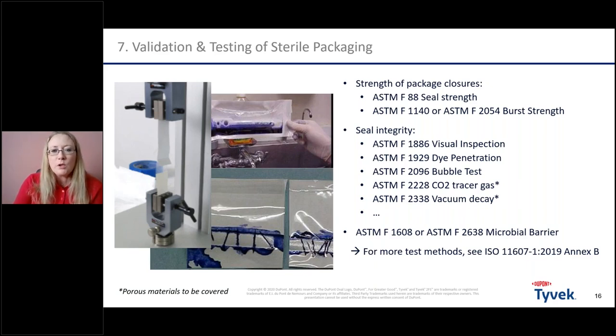Some also use burst strength testing, an overall strength test to see how much pressure the packaging can withstand. Then you need to evaluate seal integrity or integrity of the packaging - there are different tests here. What's usually done a lot is dye penetration testing, F1929, or bubble testing, which is a whole package test, a bit more gross leak, but good for post-transportation evaluation. There are also new tests like vacuum decay, etc., on the market.